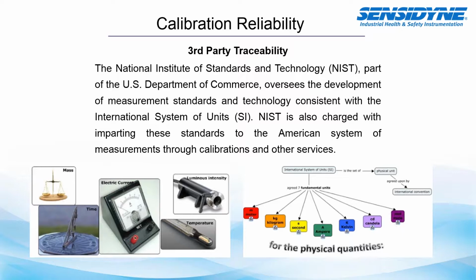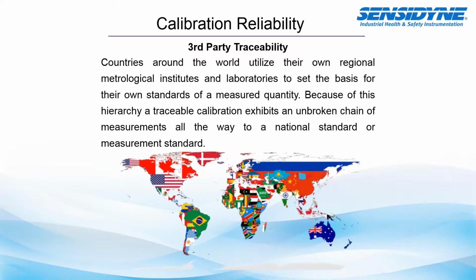So these NIST standards will really make sure that when we say a foot is a foot, a pound is a pound, a kilogram is a kilogram, 1 second of time is 1 second of time, everything is aligned to this national standard, which then can be realigned to worldwide standards. So countries around the world will utilize their own regional metrological institutes and laboratories to set the basis for their own standards of measurements. Because of this hierarchy, a traceable calibration will exhibit an unbroken chain of measurements all the way to this national measurement standard.